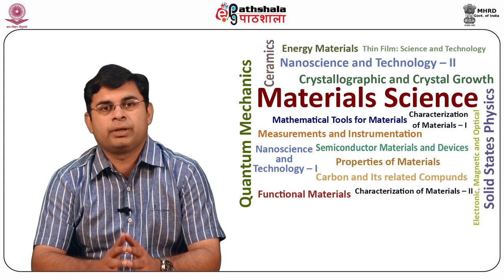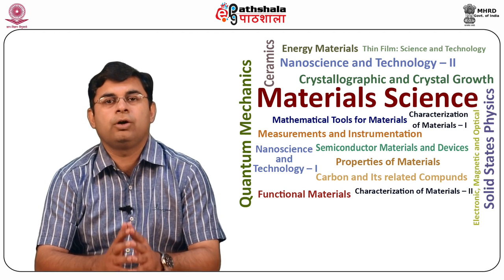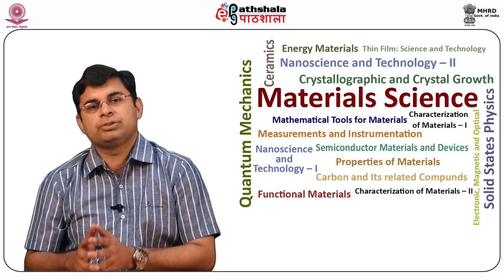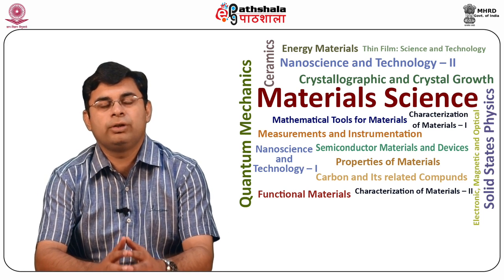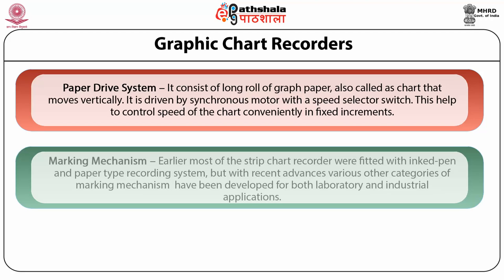In strip chart recorders, one or more variables are recorded with respect to time, so they are also called XT recorders. The first component is the paper drive system, which consists of a long roll of graph paper — also called a chart — that moves vertically. It is driven by a synchronous motor with a speed selector switch, which helps control the speed of the chart conveniently in fixed increments.